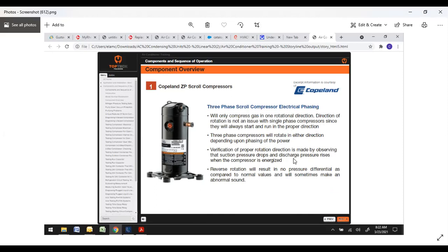Verification of proper rotation direction is made by observing that suction pressure drops and your discharge pressure rises when the compressor is energized. Reverse rotation will result in no pressure differential as compared to normal values. If it's running backwards, just switch one of your legs of power, and that will reverse the phase.